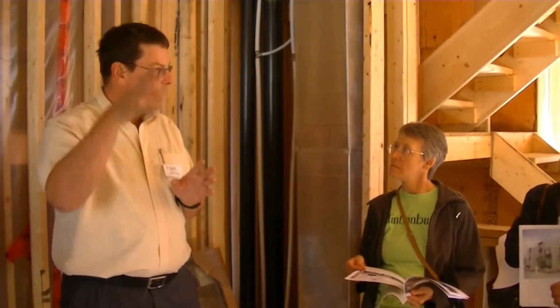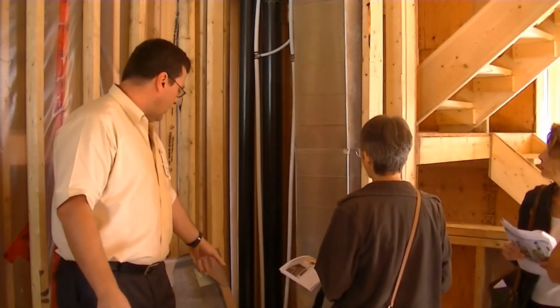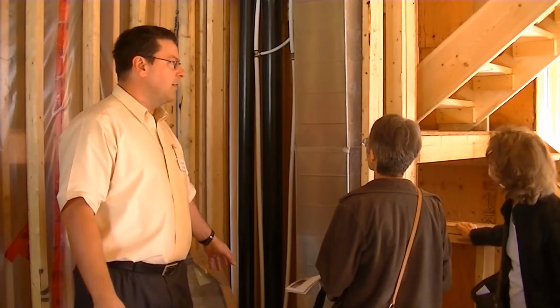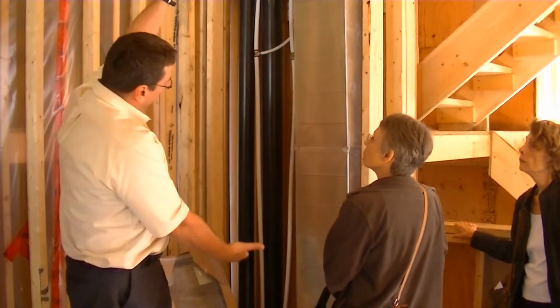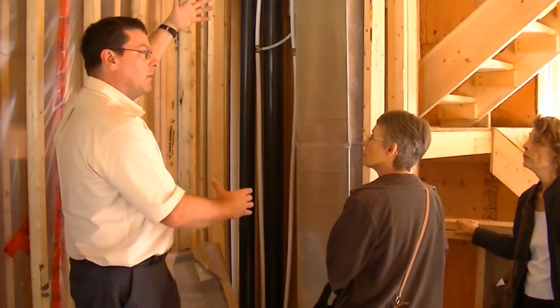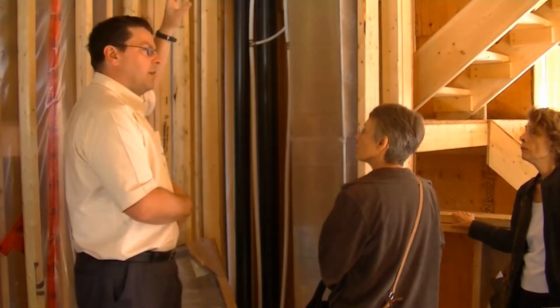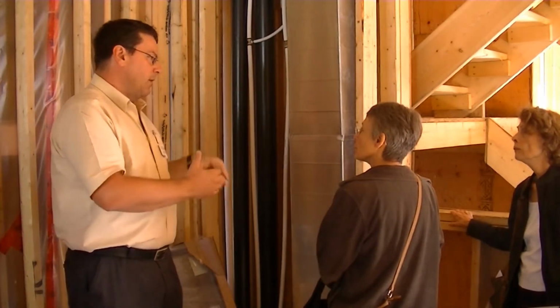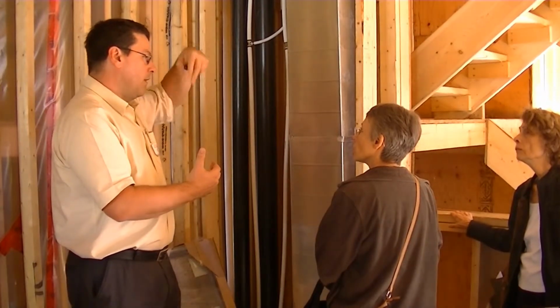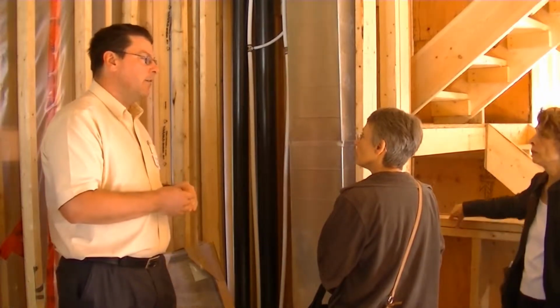And then we're linking it with a drain water heat recovery on the stack. So this is your sanitary stack. In the basement, it's not in there now because people tend to steal copper in houses that aren't locked up. So at some point we'll just cut a piece of the stack about this high and put it in this big copper tube. When you're showering, which is mainly when it's best to exchange, your warm water is running down the pipe, the cool water is running up around it, and it takes 50%. You get some very high efficiencies.